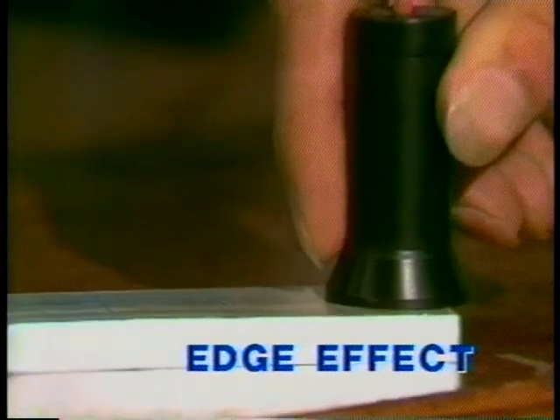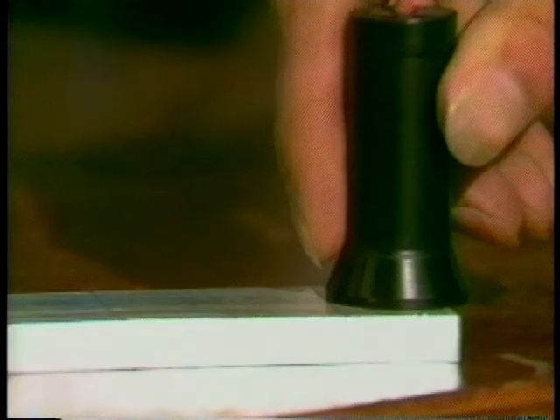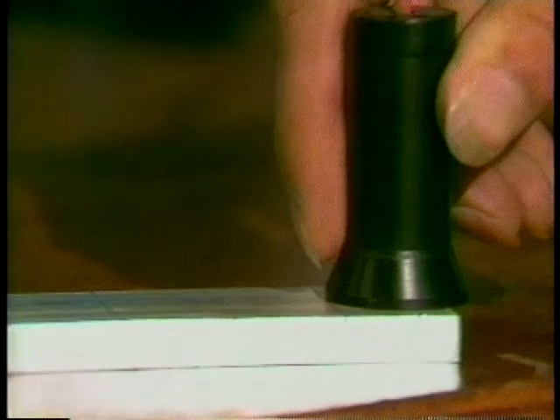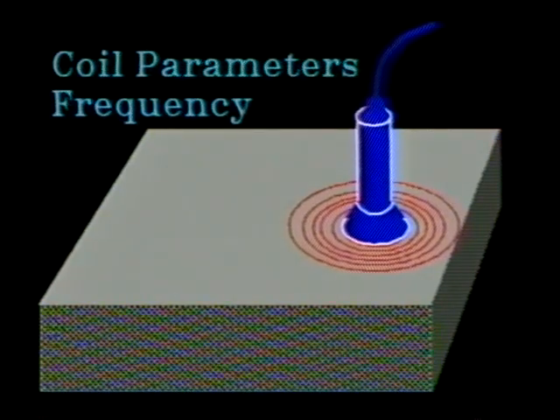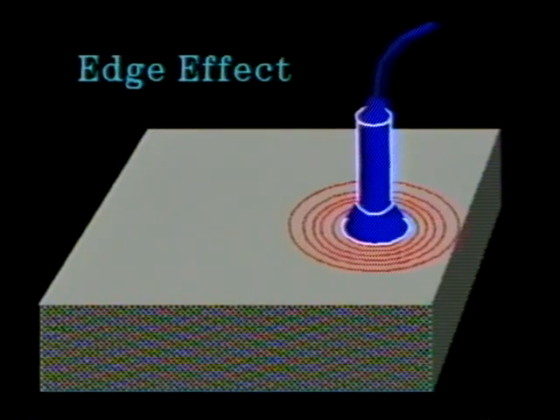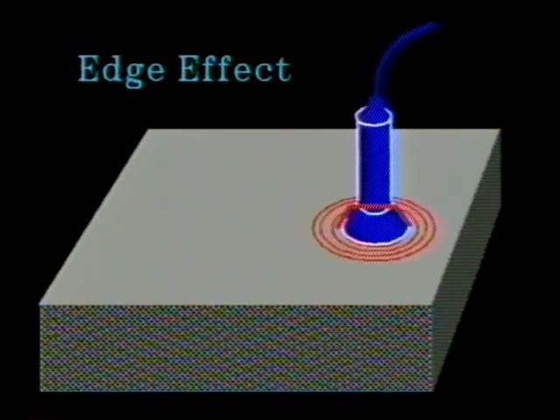The electromagnetic field produced by an excited test coil extends in all directions around the coil. As test objects' geometrical boundaries are approached by the test coil, they are sensed by the coil prior to the coil's arrival at the boundary. The coil's field precedes the coil by some distance, which is determined by coil parameters, operating frequency, and test object characteristics. As the coil approaches the edge of a test object, eddy currents become distorted by the edge signal. This is known as edge effect. Response to the edges of test objects can be reduced by the incorporation of magnetic shields around the test coil, or by reducing the test coil diameter. Edge effect is a term most applicable to the inspection of sheets or plates with a probe coil.